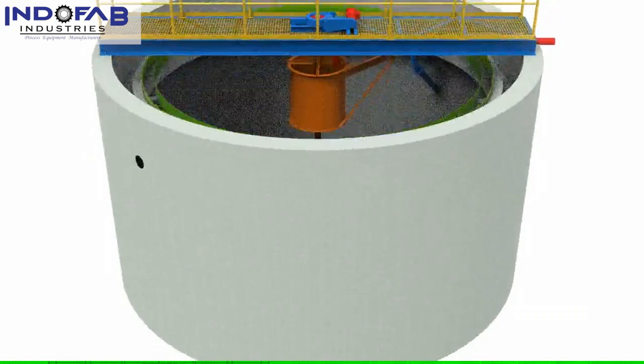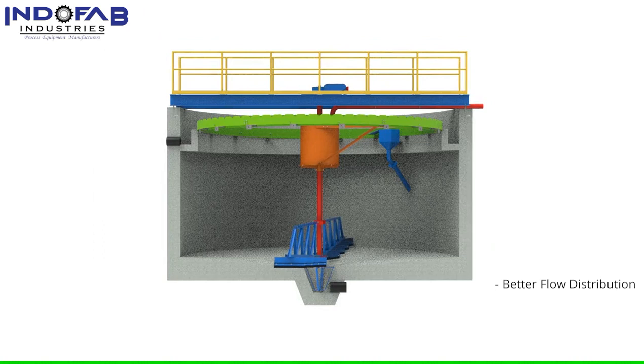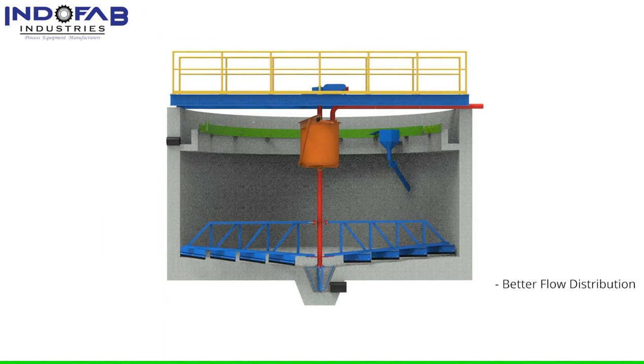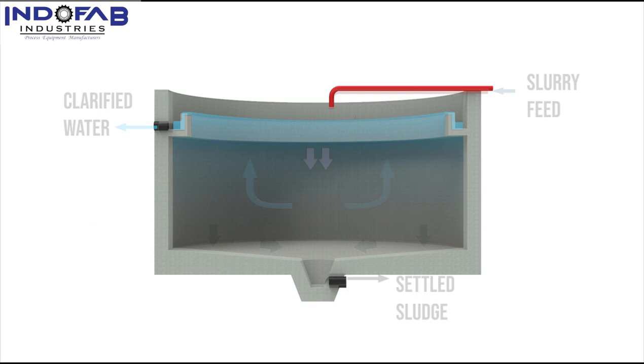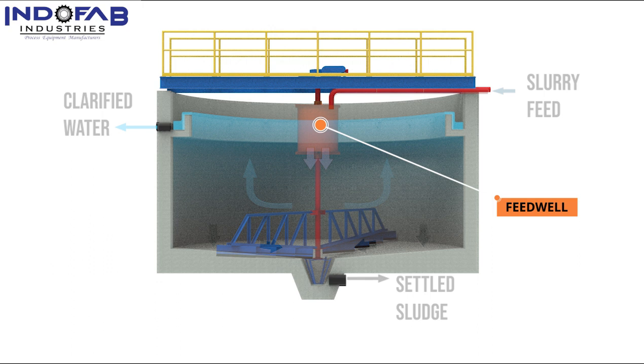There is a wide variety of circular clarifiers. This is a centrally driven circular clarifier with skimmer. It is generally preferred because of the better flow distribution. Let's take a look inside the tank to understand further. The slurry or suspension enters the tank approximately in the center through the red feed pipe. Most of the kinetic energy is absorbed by the energy dissipating feedwell, which, being partially submerged, also restricts the surface disturbance to the tank.